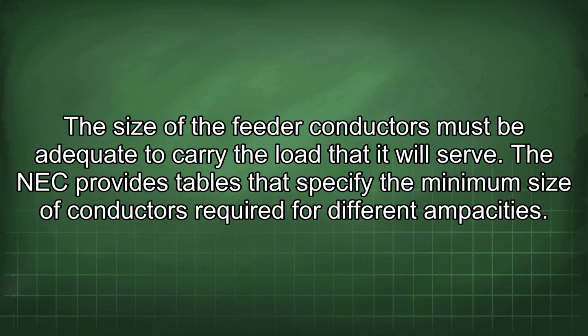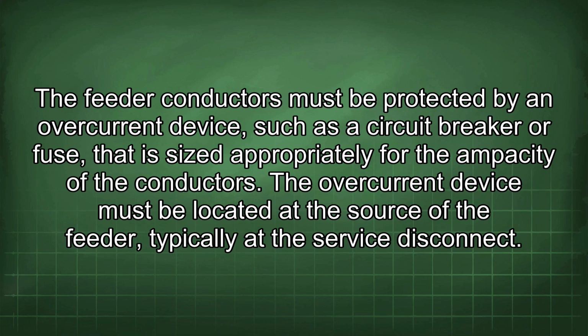The size of the feeder conductors must be adequate to carry the load that it will serve. The NEC provides tables that specify the minimum size of conductors required for different ampacities. The feeder conductors must be protected by an overcurrent device, such as a circuit breaker or fuse, that is sized appropriately for the ampacity of the conductors.